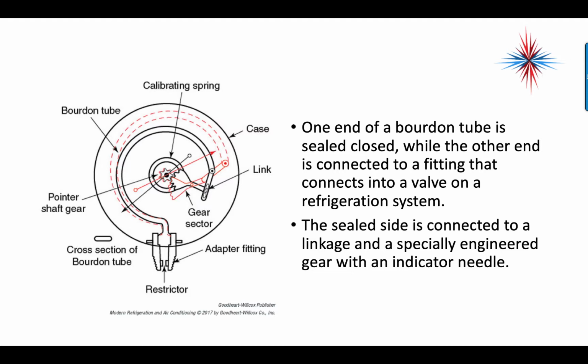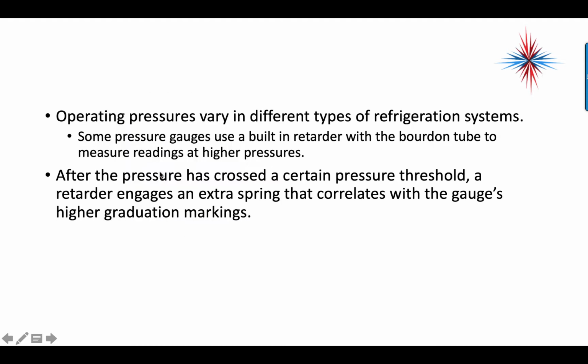So one end of the Bourdon tube is sealed closed, okay? That is all the way at the end. The other end is connected to a fitting that connects into a valve on the refrigeration system. So again, this is the original shape of the tube. Now, the sealed side is connected to the linkage with a special engineered gear with an indicator dial. So what we have here is our gear that turns, okay, and the dial is connected to that gear. As the pressure inside the tube increases, it becomes bent out of shape. And that bending action will actually drive that gear either clockwise or counterclockwise.